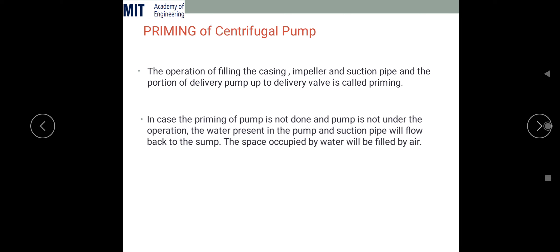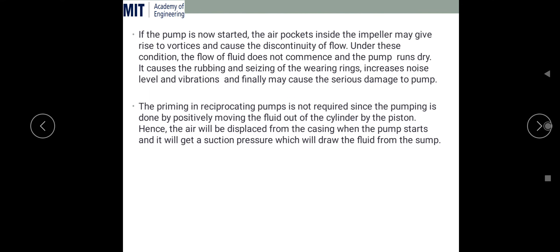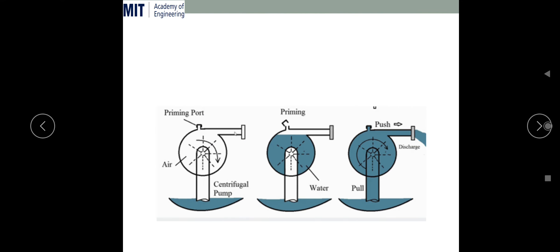Now, what is priming of a centrifugal pump? Priming is the operation of filling the casing, impeller, suction pipe, and the delivery pipe up to the delivery valve with liquid before starting the pump. Initially, when the pump is about to start, there is air inside the casing, and the pump has to transfer water. Due to the presence of air, it is not able to transfer liquid from the sump to the delivery point.